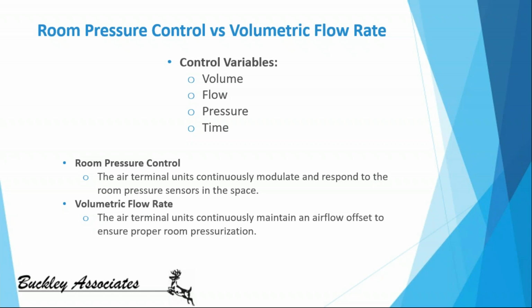How large is the room? Do we have a tightly constructed room? What is our air leakage rate in the space? How long was the door open? You can even say, how long did it take to meet the pressure set point? Did we overshoot or undershoot that set point? There are a lot of questions to be answered. That's if we're driving on room pressure.